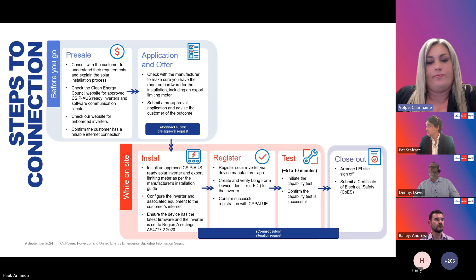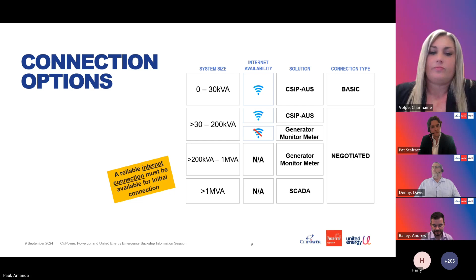Moving to the next slide, this is a summary of what we've just discussed in terms of connection options. For system sizes that fall within 0 to 30 kVA, they need to be CSIP-AUS compliant and connected with internet. For sites greater than 30 up to 200 kVA, they must either be CSIP-AUS compliant with internet or be connected via a generator monitor meter.